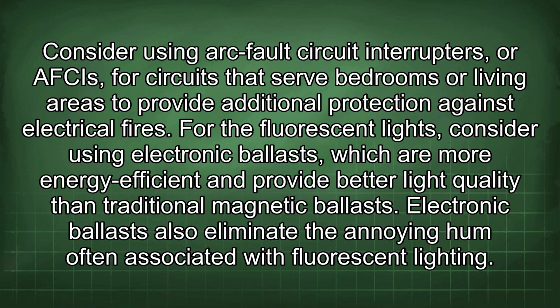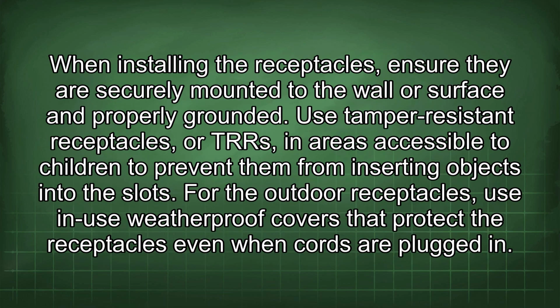energy efficient and provide better light quality than traditional magnetic ballasts. Electronic ballasts also eliminate the annoying hum often associated with fluorescent lighting. When installing the receptacles, ensure they are securely mounted to the wall or surface and properly grounded. Use tamper-resistant receptacles, or TRRs, in areas accessible to children to prevent them from inserting objects into the slots.